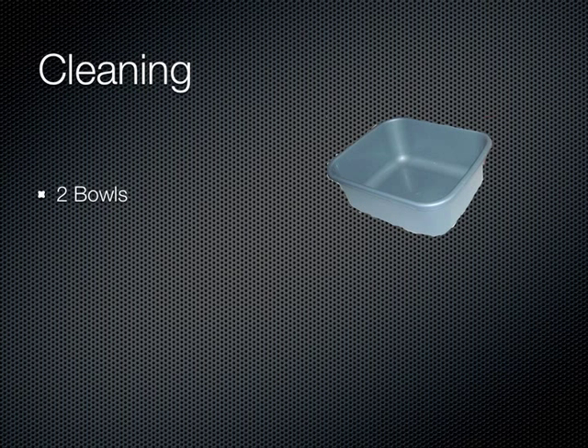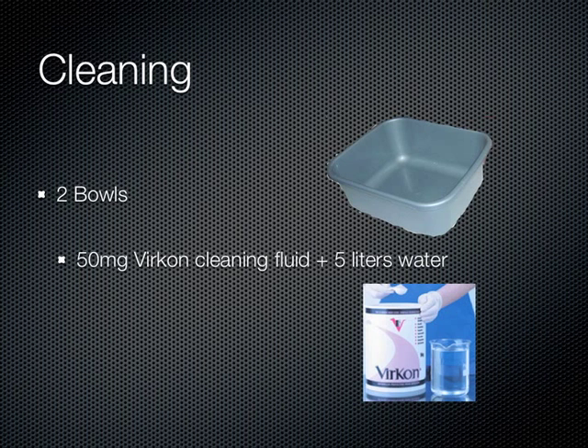Two washing bowls should be set up to clean the equipment. One should contain 50 mg of Virkon cleaning fluid and 5 liters of water, and the other should have water to rinse the equipment after it has been immersed in the Virkon solution for 10 minutes.